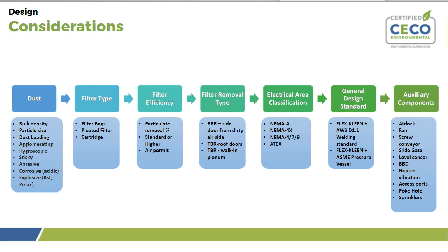Electrical area classification goes hand in hand with the type of dust. In combustible or non-combustible dust applications, the electrical classification must be rated accordingly. Typical classifications include NEMA 4, NEMA 4X, NEMA 4/7/9, or ATEX — with ATEX being more of a European certification. Within those classifications, you will hear about classes, groups, and divisions, such as Class I or Class II.